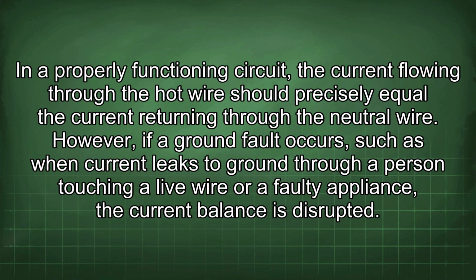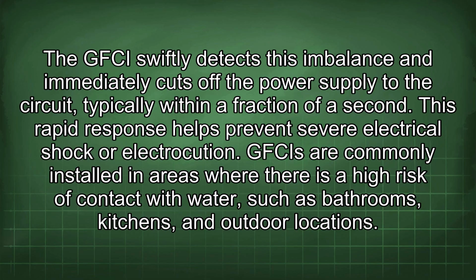In a properly functioning circuit, the current flowing through the hot wire should precisely equal the current returning through the neutral wire. However, if a ground fault occurs, such as when current leaks to ground through a person touching a live wire or a faulty appliance, the current balance is disrupted. The GFCI swiftly detects this imbalance and immediately cuts off the power supply to the circuit, typically within a fraction of a second. This rapid response helps prevent severe electrical shock or electrocution.